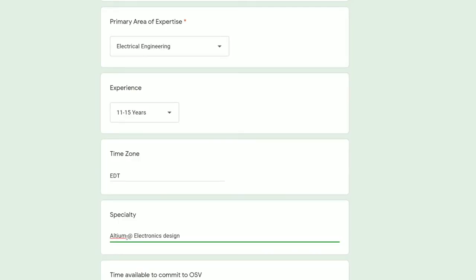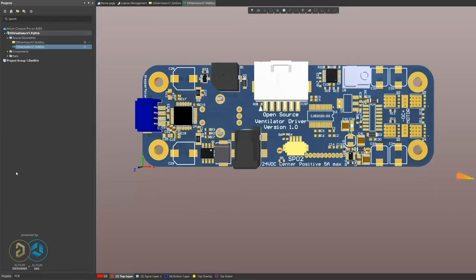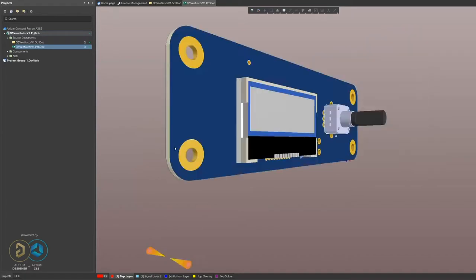The Git had specific approvers in each area. In terms of hardware and electronics direction, we needed to give the team a system circuit. We had to monitor temperature and humidity, tidal volume, respiratory rate, intake, exhale ratio, plateau airway pressure, driving pressure, and PEEP. We put out a detailed survey form to capture people's skill sets, interests, and experience — that's how we picked the team to work on the Altium project for the electronics. The development team, regardless of where they were, was all working on the same design with version control.